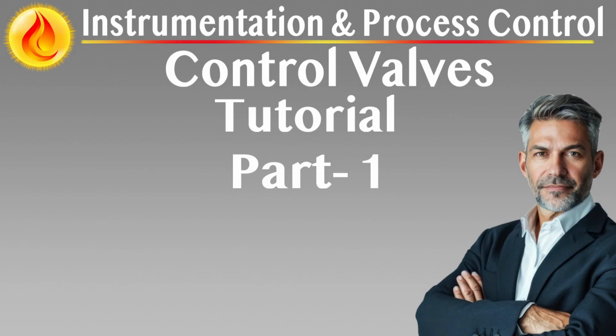Valve bonnets must be bolted and use fully retained gaskets. Gasket selection shall comply with standard design specifications. Bonnet designs must enable full top access to internal trim assemblies for maintenance.